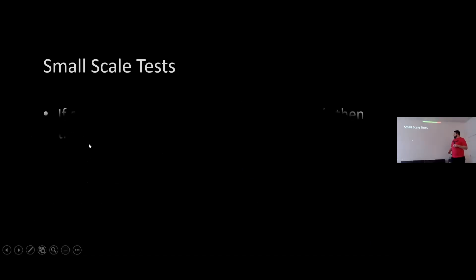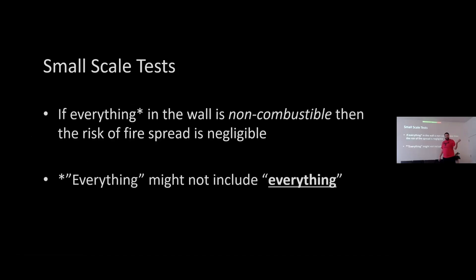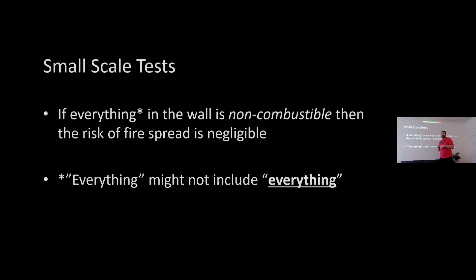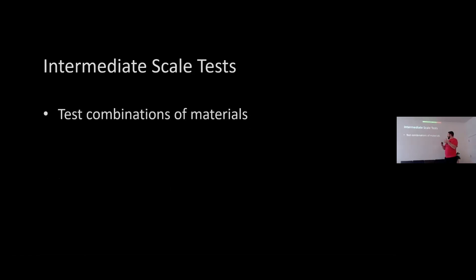When we look at the whole cladding system on small scale tests, if everything in the wall is non-combustible then it's probably not going to catch fire. The term 'everything' has quotes around it — certain things are exempt depending on how you read certain codes, which is where it starts to get gray. If you can prove everything in your wall is not going to burn, you're pretty much safe. If you do include something combustible, you need to go to the next step — the larger test — where you start looking at how combinations of materials work together: how you layer them to stop fire spreading, and whether two combustible materials combine to make a super-combustible material.